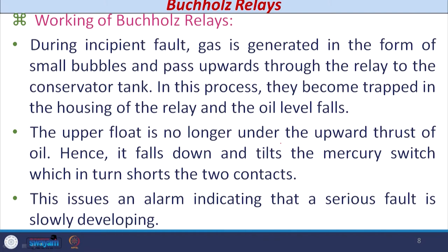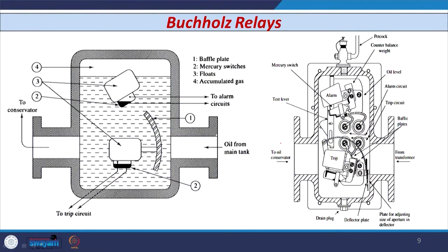During an incipient fault, gas is generated in the form of small bubbles and they pass upwards to the relay. Whenever they become trapped in the housing of the relay, the oil level falls. There are two floats: the upper float is meant for the alarm circuit — to indicate an alarm so the operator can take a decision — while below the lower float, a mercury switch is provided for the tripping circuit. Whenever gas or bubble formation is large, the lower float comes into picture, whereas when bubble formation is very slow, the upper float comes into picture.